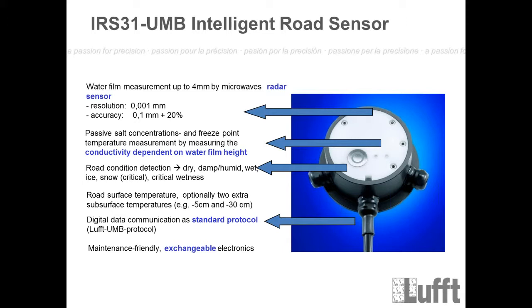One other important thing for this measurement is that it is a passive measurement. That means this sensor, this IRS31, is adjusted to natrium chloride. So you need to use natrium chloride, sodium chloride solutions, to check the sensor itself. That's the second one, and these two measurements, the water film and the freezing point, will be part of the IRS31 calibration kit. Then we have the last important measurement, which is the surface temperature measurement.